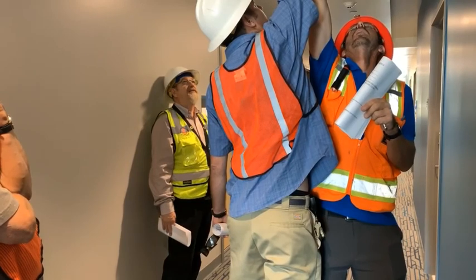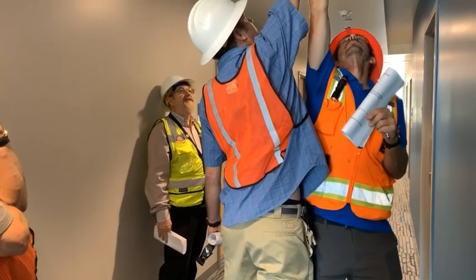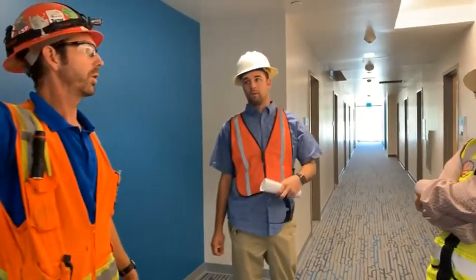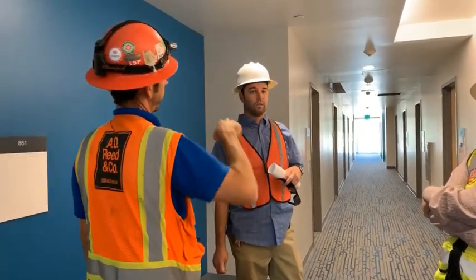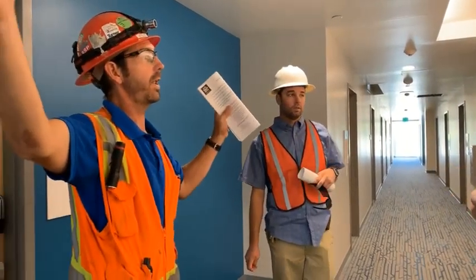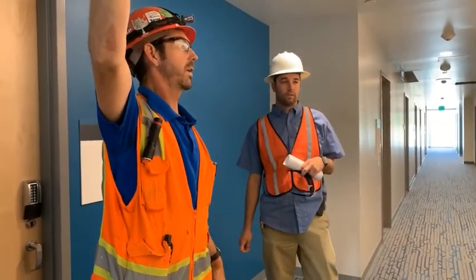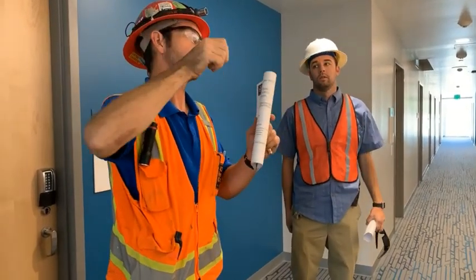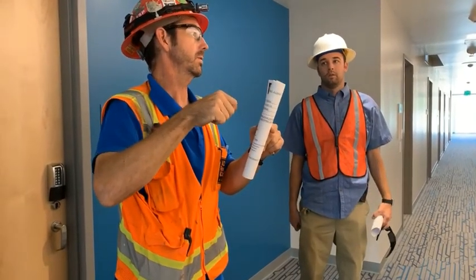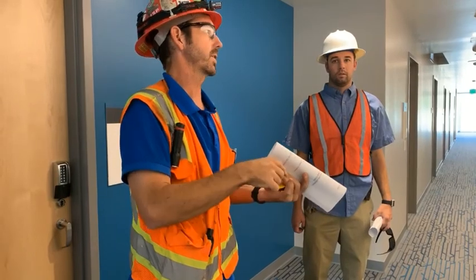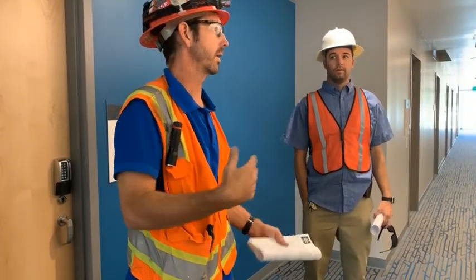It's like a super long screwdriver. If it's cold, then obviously something is wrong with it, so go to the next one. If those are hot, then it's probably something here. So then you could take that out of the piping system with the unions and make sure the check valve opens. Make sure there's no debris stuck in the thermostatic device.